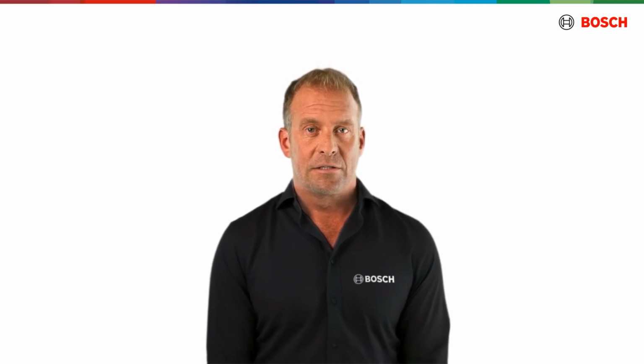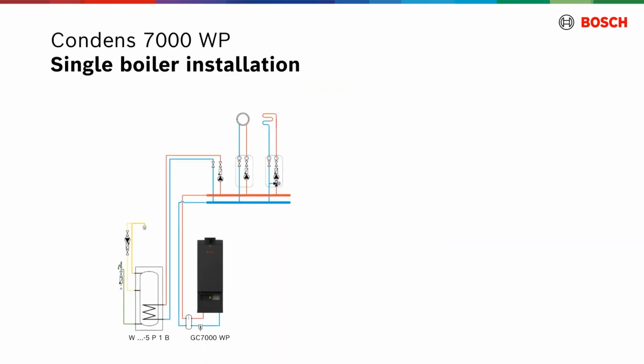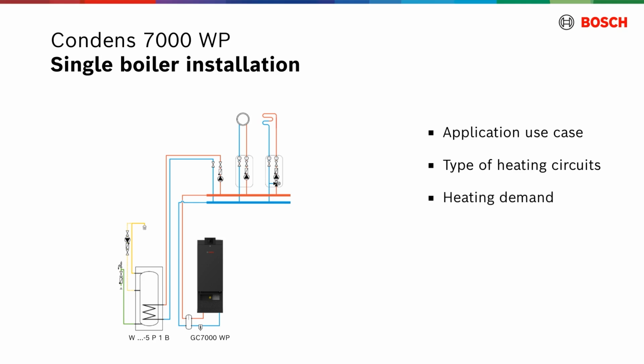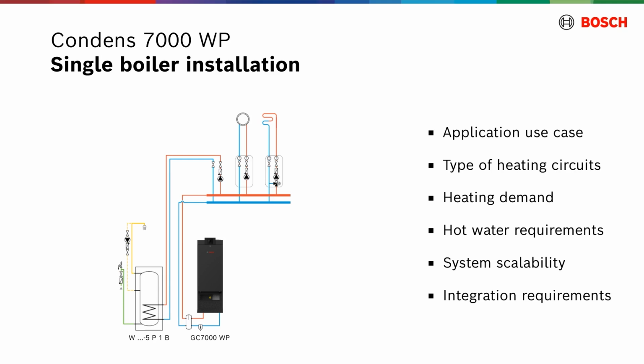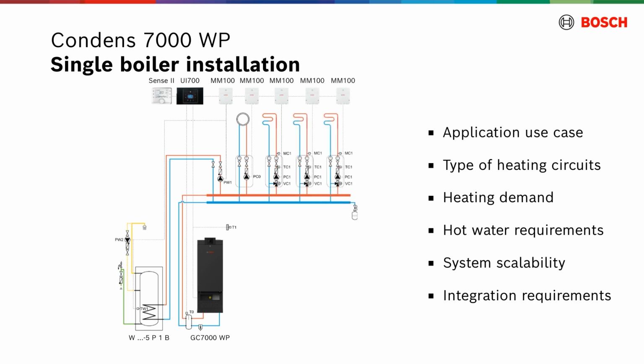For the heating installations, choosing the right combination of system controller and function modules ensures optimal performance. When selecting a system controller for a single boiler installation, you should consider factors such as application use case, number and type of heating circuits, as well as heating demand and hot water requirements. System scalability and integration into building management system are also important for the correct decision. Weather compensation controller Sense2 offers extensive compatibility, while function modules MM100 ensure additional control. Further modules can extend the system's capabilities, but expansion is limited based on control unit capacity.